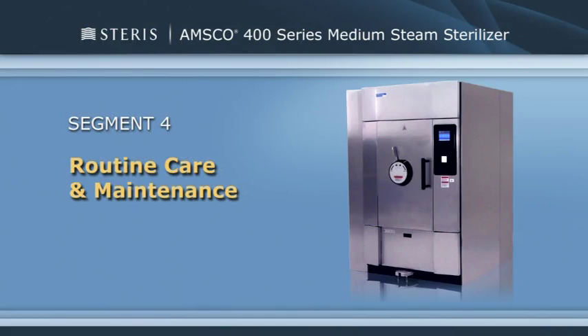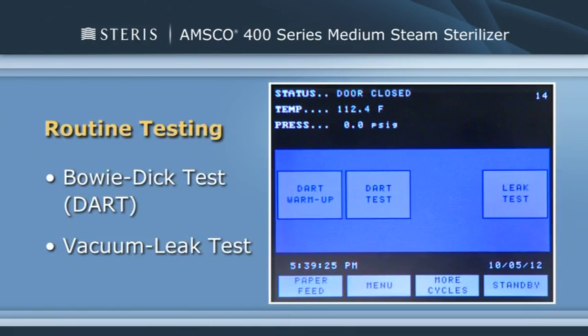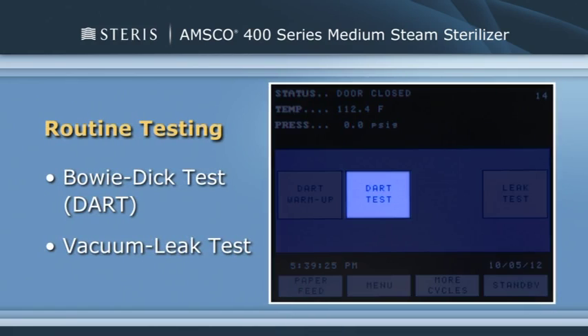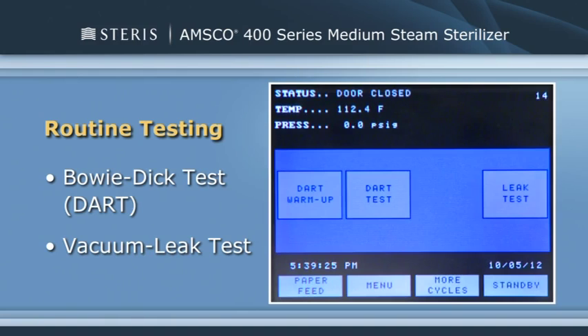Proper maintenance ensures a long and productive life for the AMSCO 400 sterilizer. In this section, we'll cover the preventative maintenance schedule and procedures for the operator. For sterilizer monitoring, you'll run a Bowie-Dick or DART test and a vacuum leak test at the beginning of each day the sterilizer is to be used.